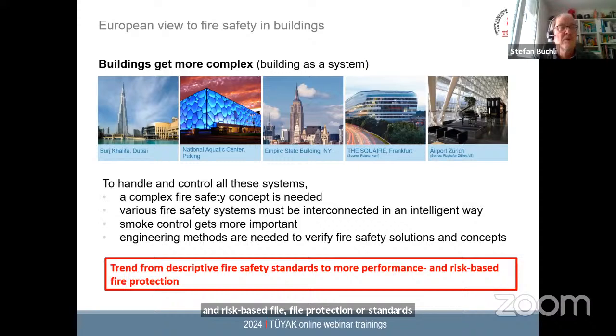This means also that more and more engineering-based methods come to action when it comes to fire safety. So you design a system, you calculate the system, for example, you use CFD, computer simulations to verify your design. And then finally, before the building goes into operation, you do live fire testing or smoke testing, for example, if you have a smoke control system. So there is a change going on, which we see more and more. Currently, for example, the Swiss standard for fire safety in buildings is under revision. And in 2026, we will have a new one. And the new one will really be very strongly performance and risk-based. So not prescriptive, descriptive anymore.